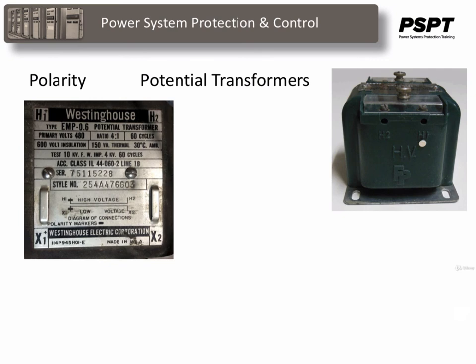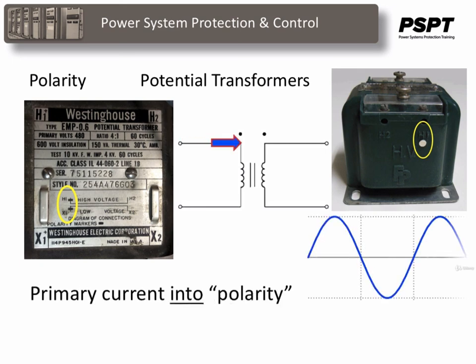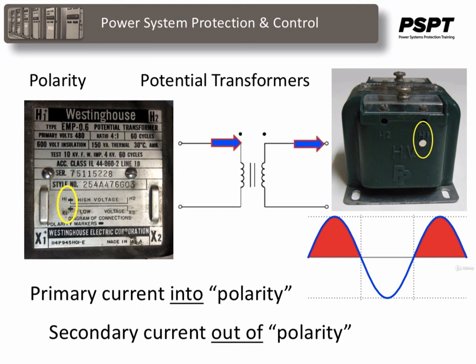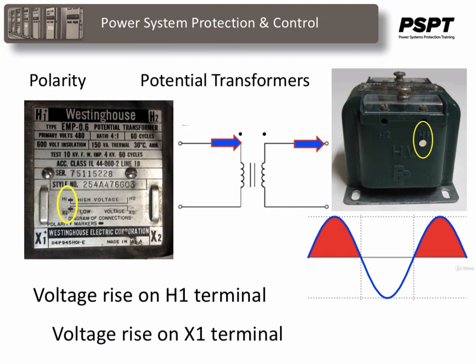Okay. Designating the polarity of a PT is very important and done much the same as in the case of a current transformer or a CT, by marking the PT primary and secondary terminals and or indicating it on the nameplate. Again, this is especially important when PTs are used for relaying or revenue meters. As in the case of the CT polarity, the primary and secondary terminals are marked in such a way that when the primary current is positive during the sinusoidal half cycle, current into a polarity, the secondary current will be out of the polarity spot. Or in terms of voltage, voltage rise on the H1 terminal gives a voltage rise on the X1 terminal.